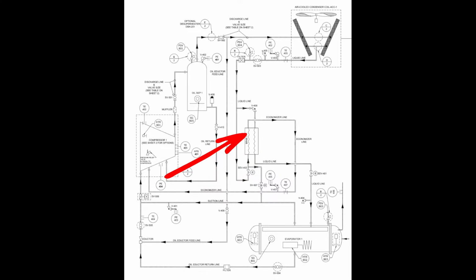So this economizer is going to function in a similar way to what you would expect to see out of like a Carrier air-cooled screw. Okay, those also use a brazed plate economizer. So do the Dunham Bushes. Those are brazed plate economizers. I think, let's see, who else uses that? Either way, those are two good examples. Carrier and Dunham Bush are two that also use this. It would be easy to reference material on.